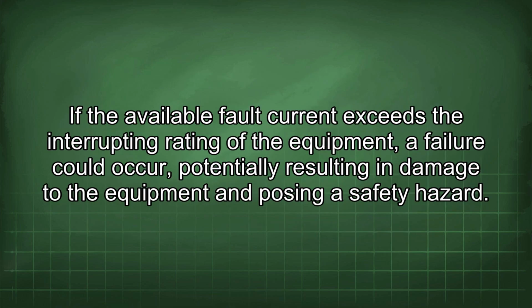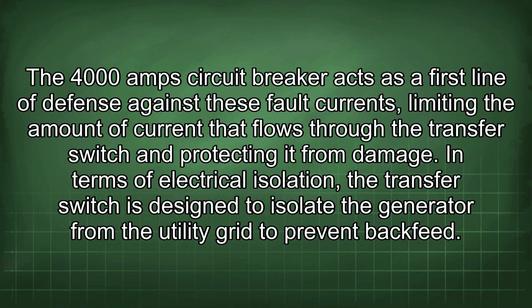If the available fault current exceeds the interrupting rating of the equipment, a failure could occur, potentially resulting in damage to the equipment and posing a safety hazard. The 4000 amp circuit breaker acts as a first line of defense against these fault currents, limiting the amount of current that flows through the transfer switch and protecting it from damage. In terms of electrical isolation, the transfer switch is designed to isolate the generator from the utility grid to prevent backfeed.